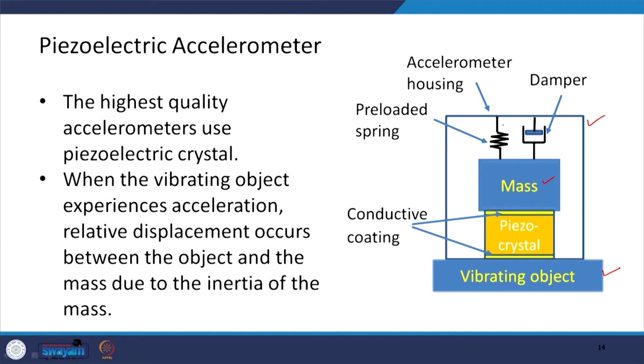a preloaded spring, a damper, and here is your piezo crystal. This piezo crystal is placed between the mass and the vibrating object, and here you can see that there are two conductive coatings. So, the highest quality accelerometers use piezoelectric crystals.